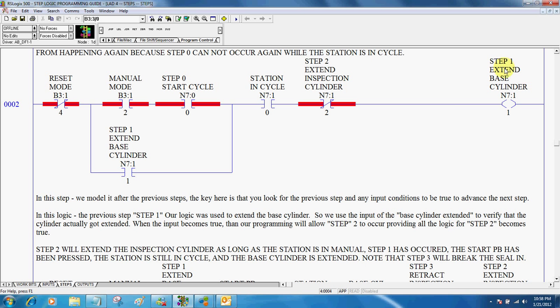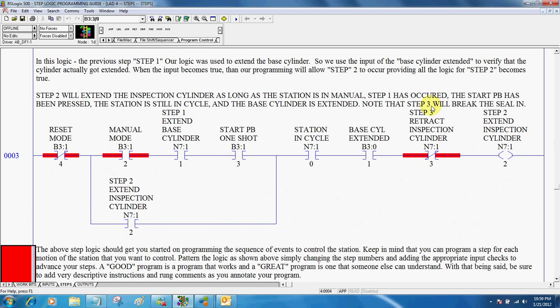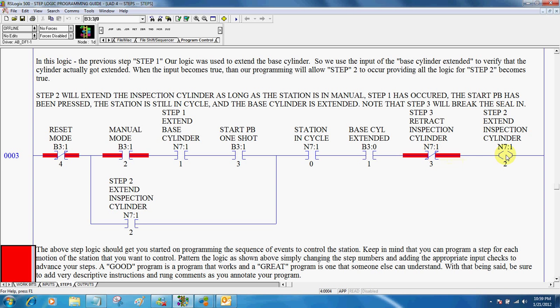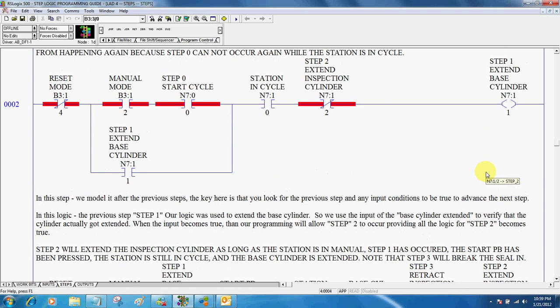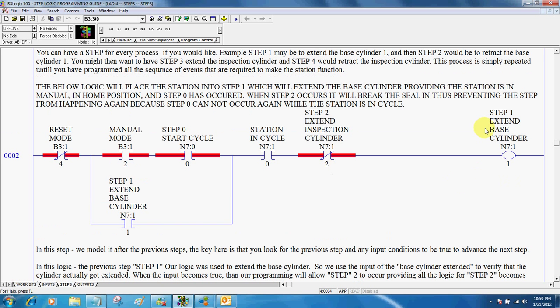In step one, we told it to extend the base cylinder. So in step two, before that can happen, it has to have become extended. And then again, step three will break this, and then step two will actually extend the inspection cylinder. So the whole key to step logic is, is we tell something to happen. Step one, we told something to happen.